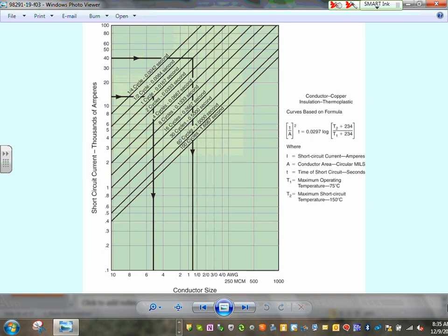This is really interesting, Adam. Look at this. Can you see that this is a 40,000 amp? I have a 40,000 amp, gentlemen. If I want the 40,000 amp to open within 1 second, can you see 1 second right in here? The conductor size has to be for 1/0. Can you see that? That's the damage curve for the conductor. The conductor size is 1/0.